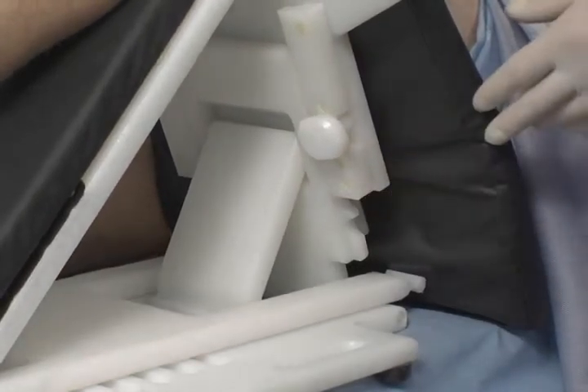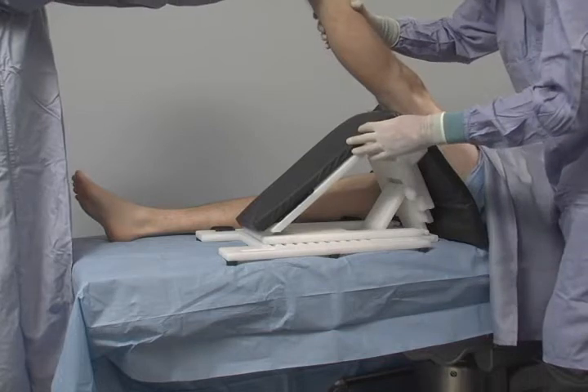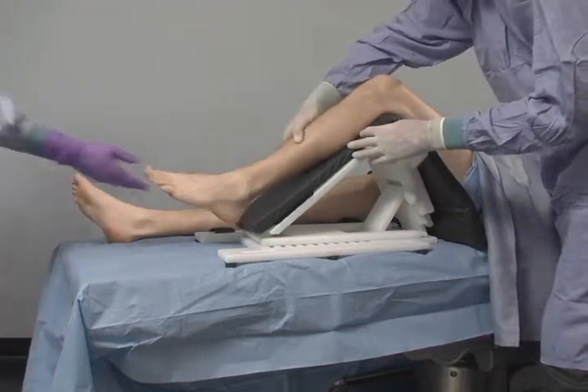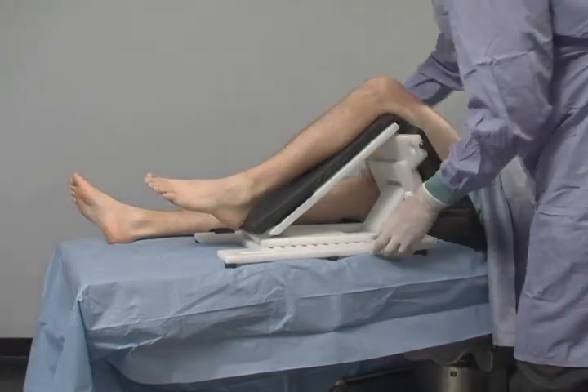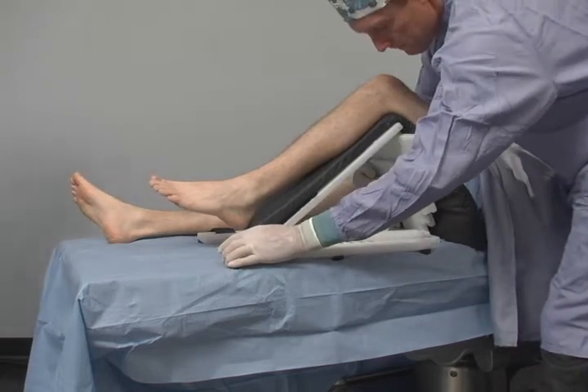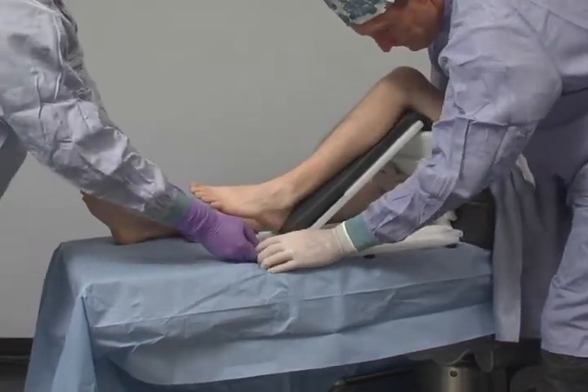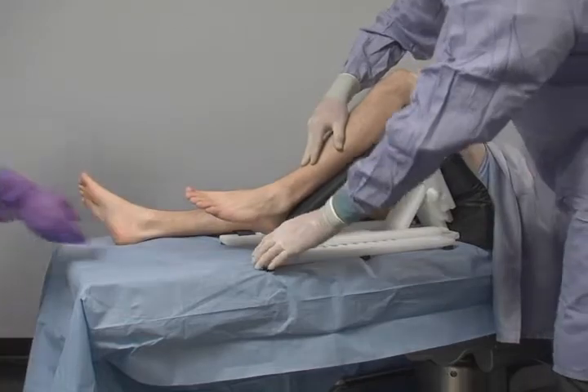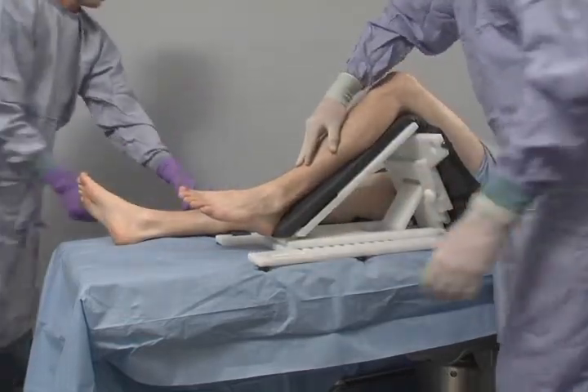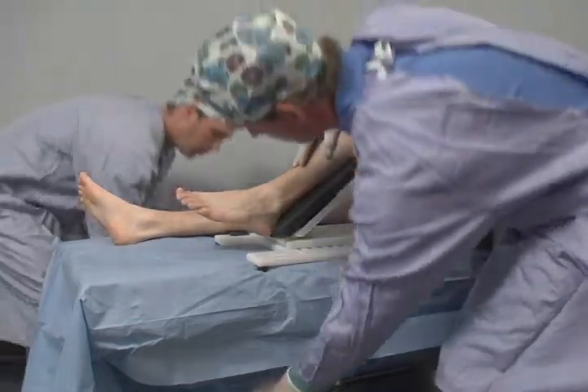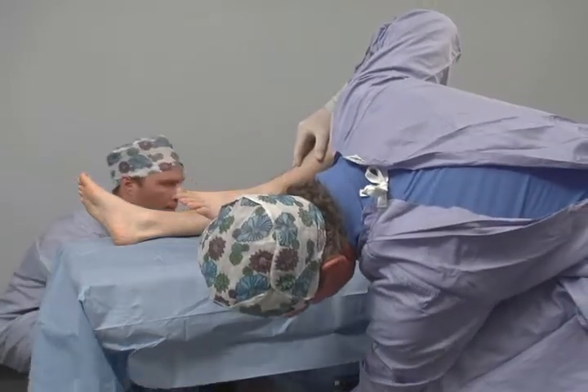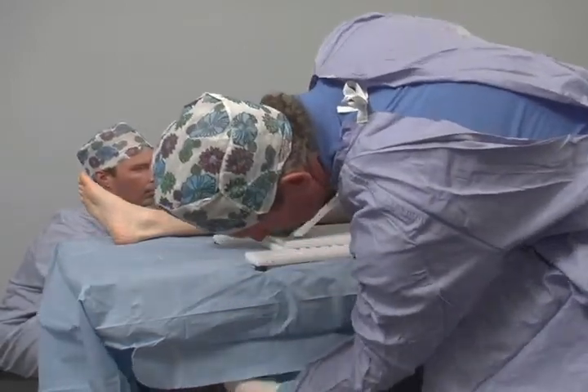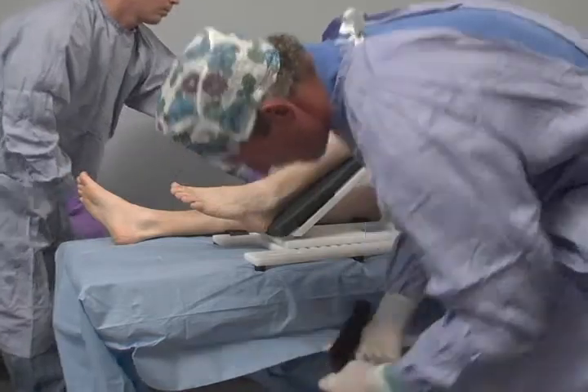There are a series of half circles on the undercarriage that the femoral adjustment cam locks into. The length should be set so that there is no pressure on the sensitive structures on the underside of the knee from contact with the apex of the TFS. After the femoral length is set, the TFS is placed firmly against the patient's buttocks. The TFS straps are wrapped around the table and attached to both sides of the TFS, securing it in place.